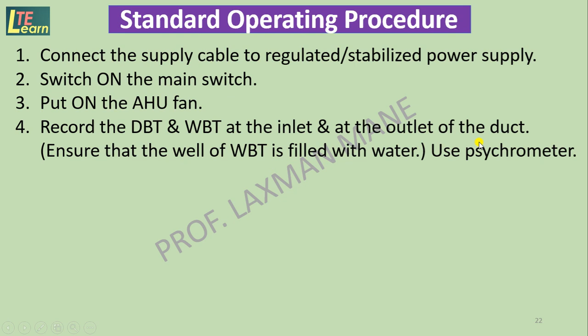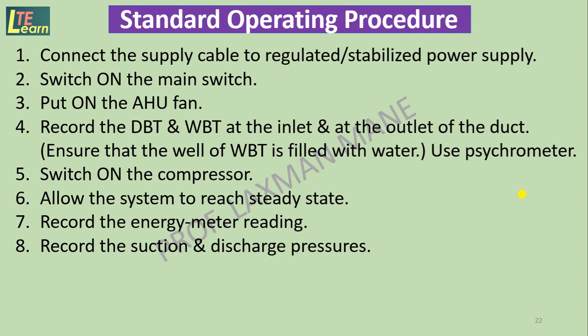After that, record the energy meter reading of the compressor. Initial and final reading of energy meter is to be taken. Record the suction and discharge pressures of compressor. Measure velocity head with the help of manometer. Take minimum 4 readings at 10 minute intervals.